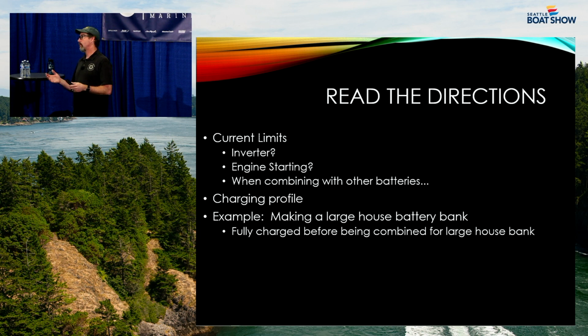Most manufacturers say if you're going to use batteries as a bank, they all need to be within 10 cycles or 50 cycles of each other. You want to do it at the same time. You don't want to have a couple of lithium batteries and go, oh, I used those for 2 years already.